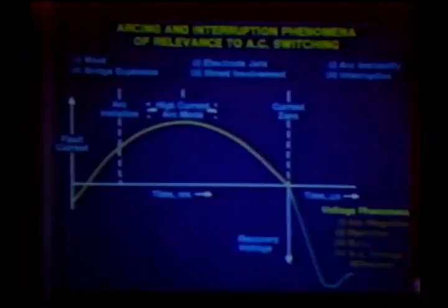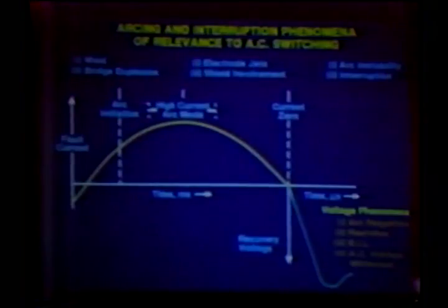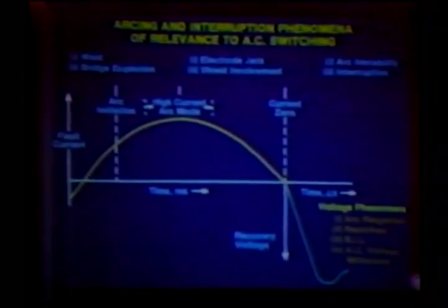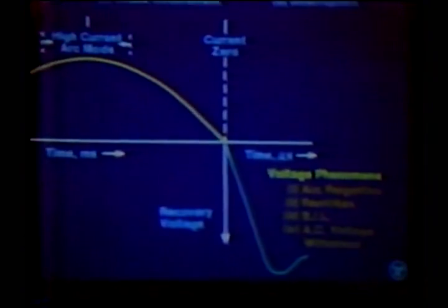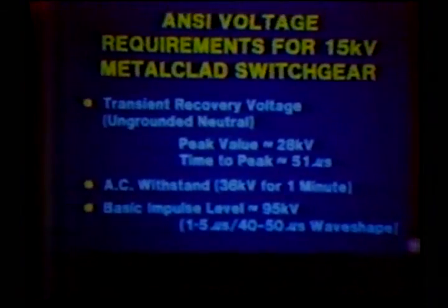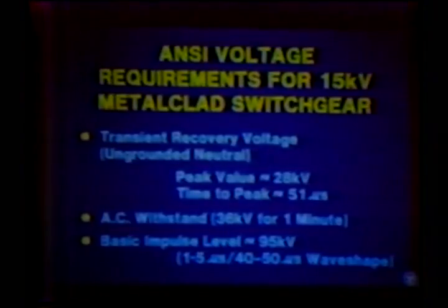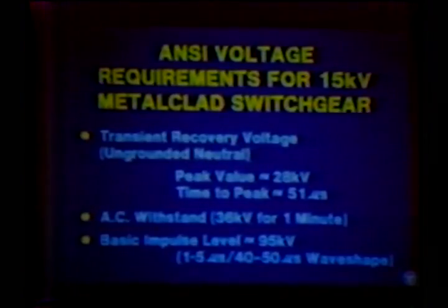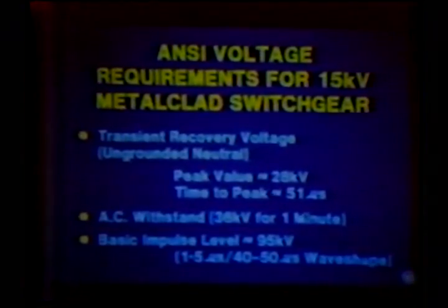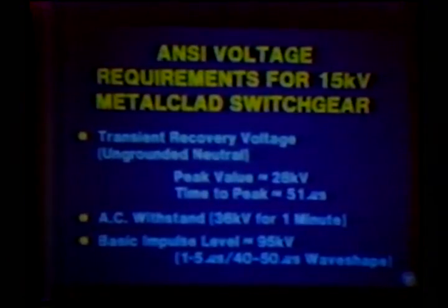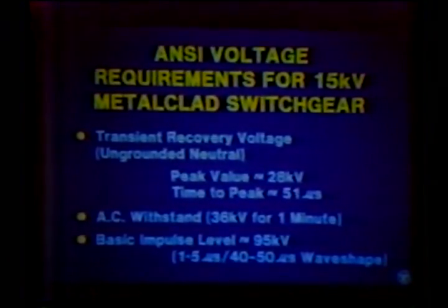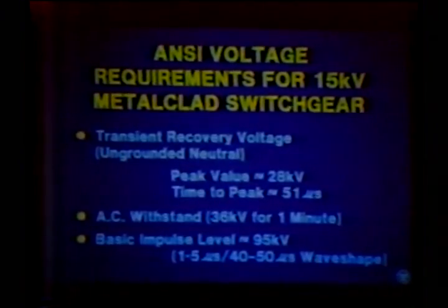The important voltage phenomena we must be concerned about are arc re-ignition and re-strikes — arc re-ignition being during the rise of the recovery voltage wave, and re-strikes being some milliseconds after current zero — as well as the basic impulse level and AC voltage withstand. For 15 kV switchgear, the transient recovery voltage requirement is that you must withstand 28 kV within 50 microseconds of current zero. The AC withstand is of a corresponding magnitude, and the basic impulse level — what value of voltage must that short gap withstand — is of the order of 100 kV for that particular application.